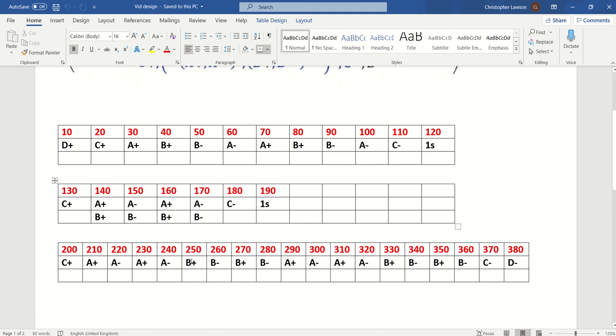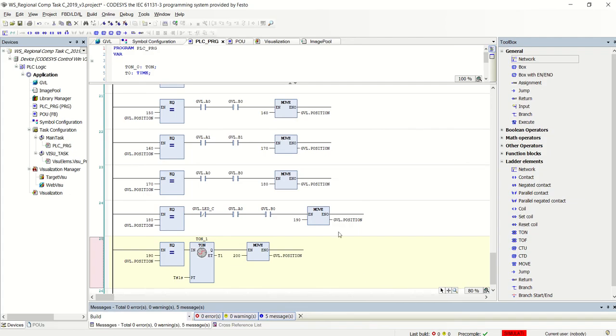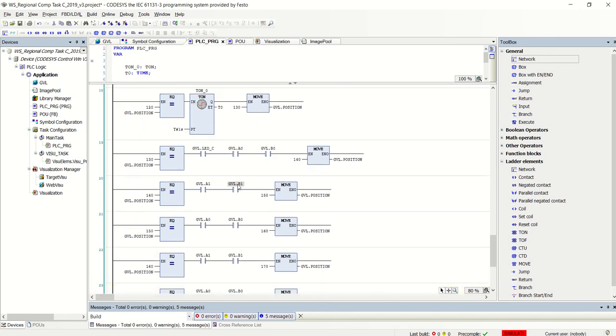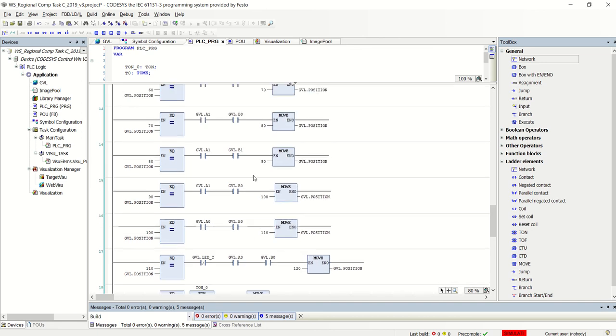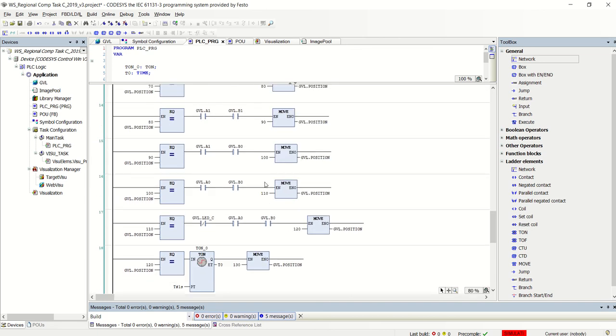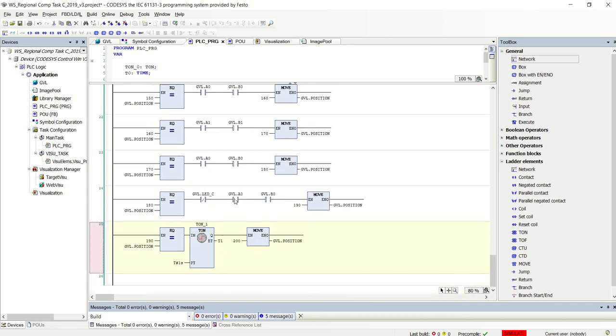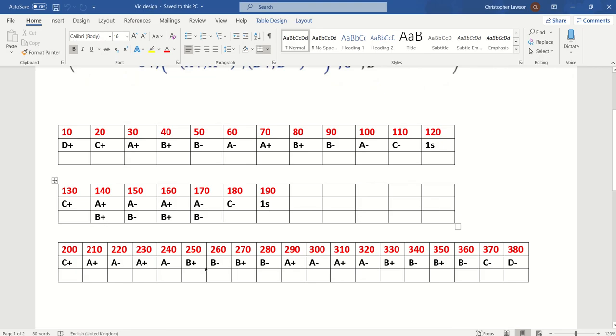which should be our next last pretty big sequence. Okay, so the only real thing I want to show you there is if you're copy and pasting your timers, use the same lines but just increment them up. So this will be now T1, and just seeing if A and B are moving forward together, just seeing how that happens both with the inputs and with the outputs. But it's all still very similar. So then just a case of testing that out and then moving on to the next sequence, this sequence down here.